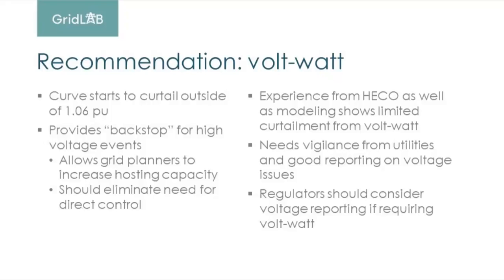And I think if states are going to make this recommendation for smart inverters, you need to make sure that there's good reporting and there's good vigilance around voltage issues, so that customers who get stuck in a situation that the utility has an obligation to remedy can have that fixed, a consistent overvoltage issue. So that's our recommendation on volt watt.